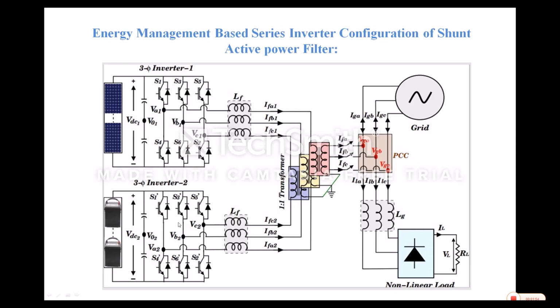Generally, a non-linear load draws power from the grid. It disturbs the current shape and also increases the THD, as we discussed. So the series inverter will inject harmonics and compensate the grid current, and it maintains the percentile THD drawn from the grid. It also injects the power which is available in the sources. Depending on the configuration, this is divided into two different conditions. One is where the available power at the sources is lesser than the load requirement power, and the second is where the available power is higher than the load requirement power. These conditions are divided into a number of modes. We can discuss them in the next slide.